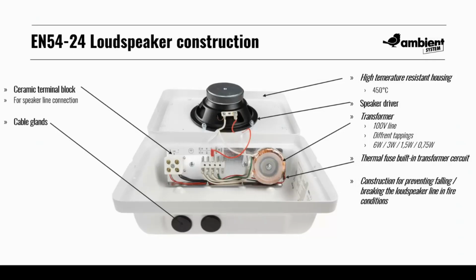So the typical loudspeaker for the voice alarm must be built in a certain specific way, so there is usually a driver, a low impedance driver, with an impedance matching transformer.